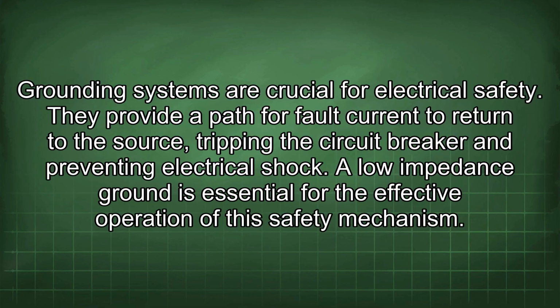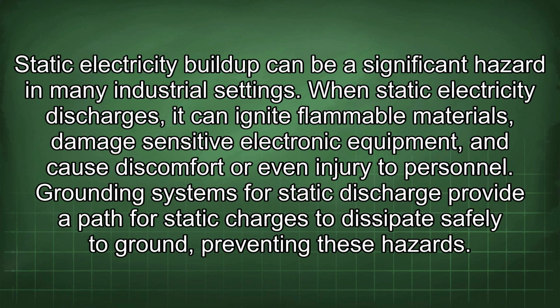Grounding systems are crucial for electrical safety. They provide a path for fault current to return to the source, tripping the circuit breaker and preventing electrical shock. A low impedance ground is essential for the effective operation of this safety mechanism. Static electricity buildup can be a significant hazard in many industrial settings. When static electricity discharges, it can ignite flammable materials, damage sensitive electronic equipment, and cause discomfort or even injury to personnel. Grounding systems for static discharge provide a path for static charges to dissipate safely to ground, preventing these hazards.